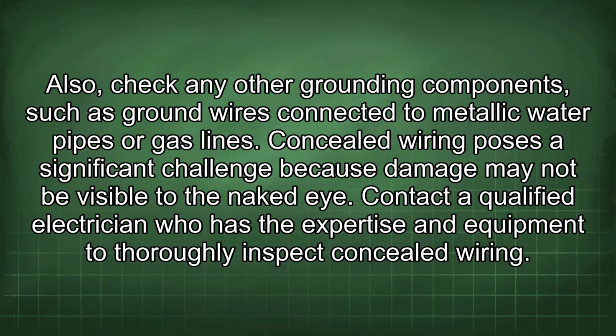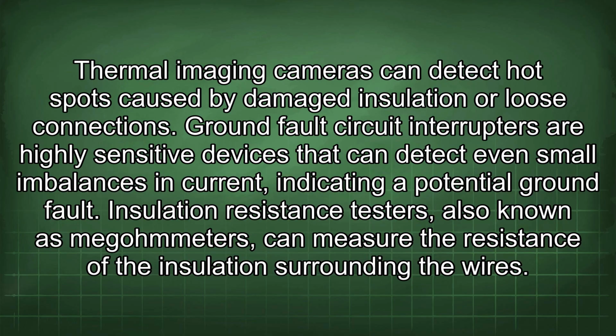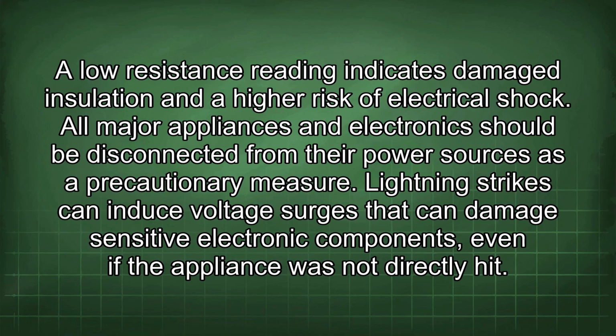Concealed wiring poses a significant challenge because damage may not be visible to the naked eye. Contact a qualified electrician who has the expertise and equipment to thoroughly inspect concealed wiring. Thermal imaging cameras can detect hot spots caused by damaged insulation or loose connections. Ground fault circuit interrupters are highly sensitive devices that can detect even small imbalances in current, indicating a potential ground fault. Insulation resistance testers, also known as megohmmeters, can measure the resistance of the insulation surrounding the wires. A low resistance reading indicates damaged insulation and a high risk of electrical shock.